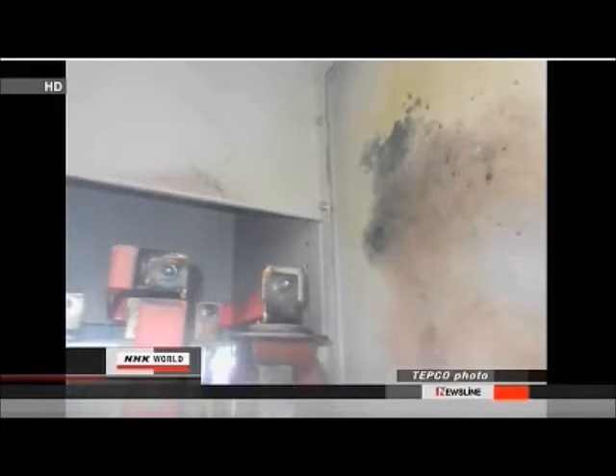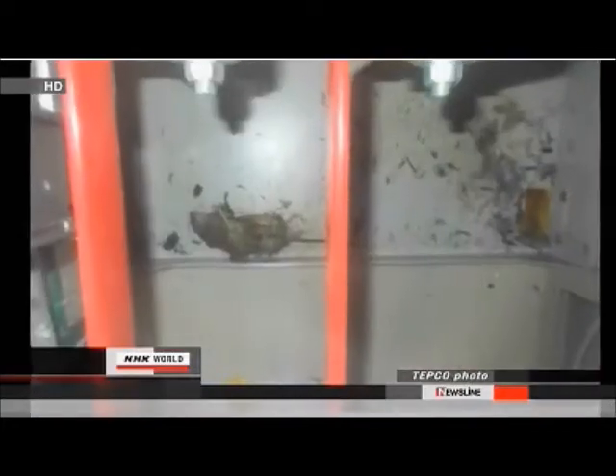They also came across a dead creature nearby that looks like a rat. They say the animal is about 15 centimeters long. Engineers believe it could have touched the terminal, causing a short circuit. They say this could have led to problems with 2 other switchboards. There's a strong possibility that this was a cause, but we're continuing the investigation to confirm what really happened.